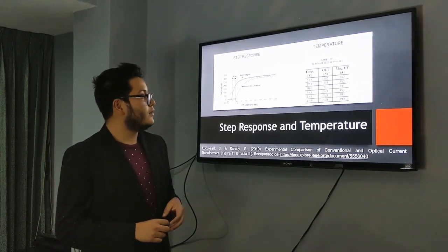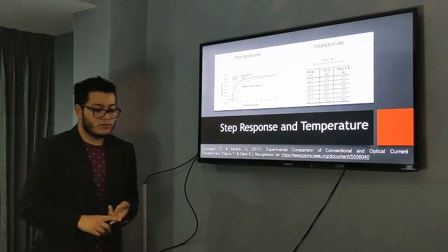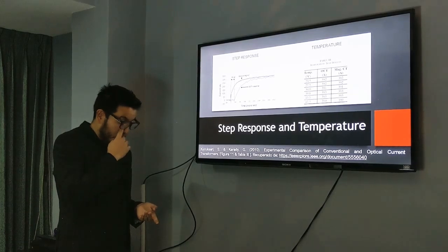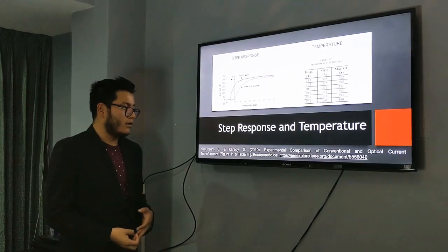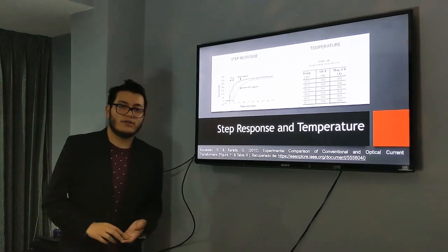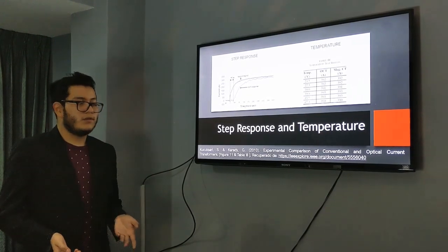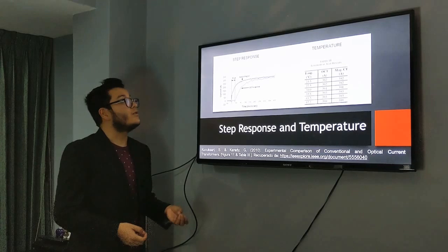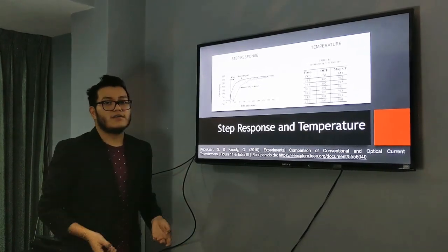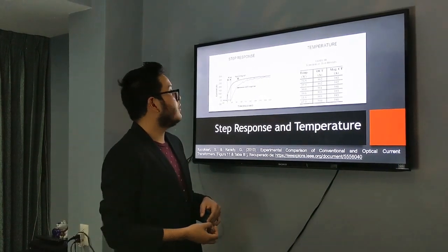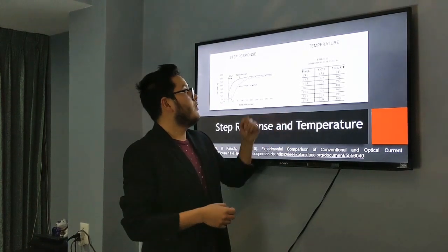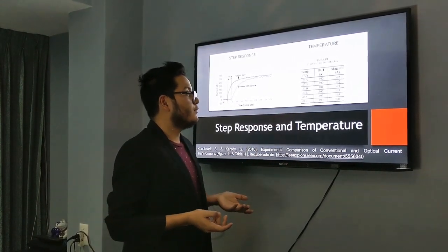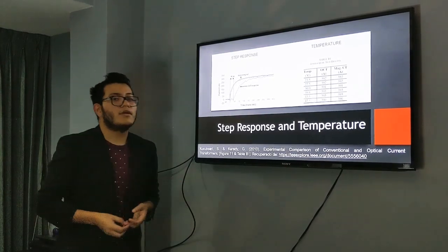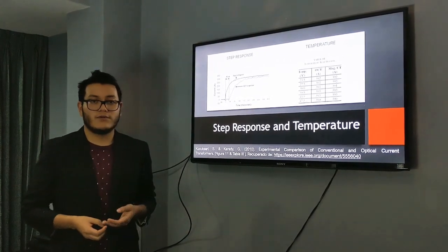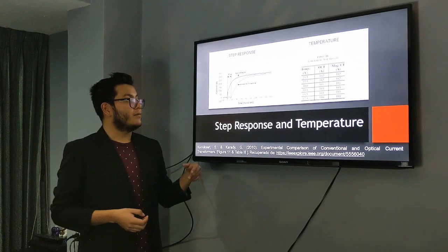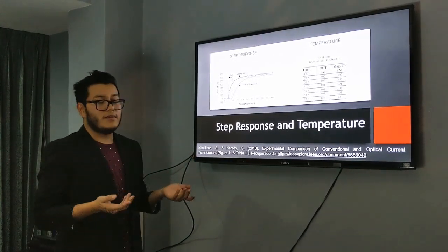And finally, the last test was temperature. In this case, temperature is known for conflicting against Faraday's effect. Optical current transformers function with Faraday's effect, so temperature is a huge point against the optical current transformer. But as we can see, if we increase the temperature, optical current transformers and conventional current transformers behave the same. So we can mention that manufacturers of optical current transformers have this problem in mind and have a response against this type of problem.